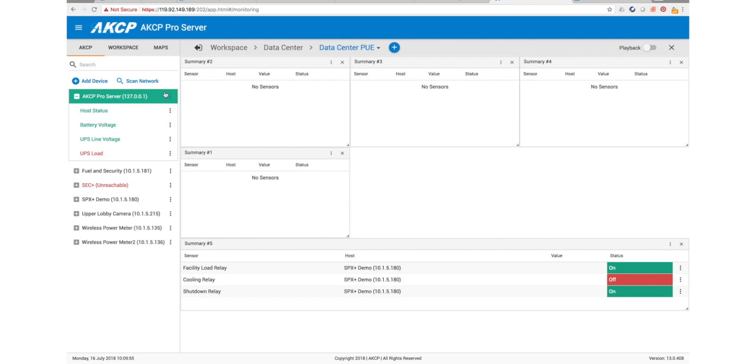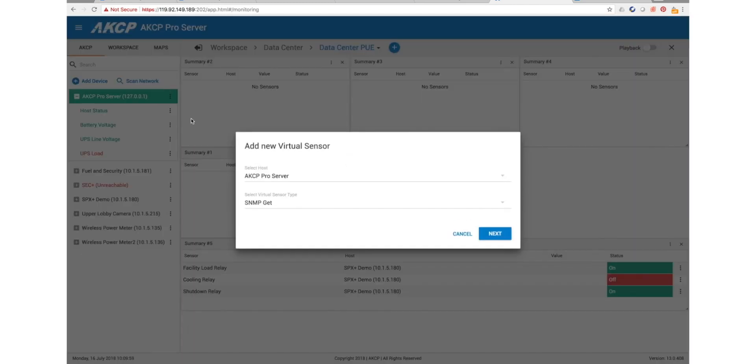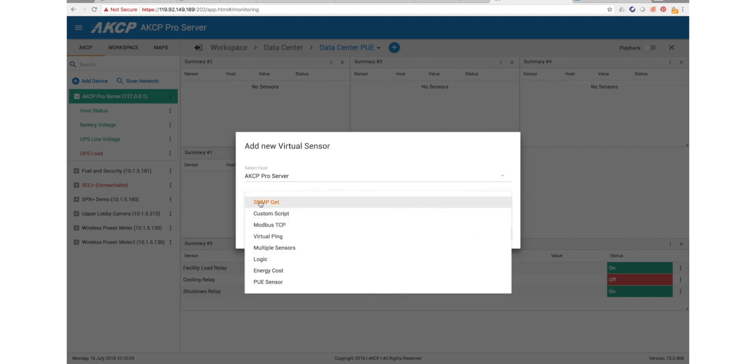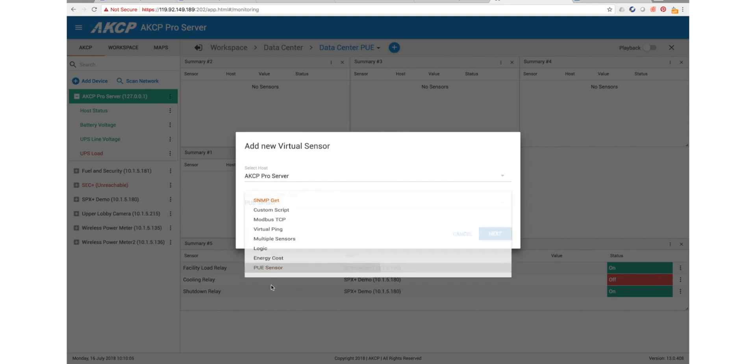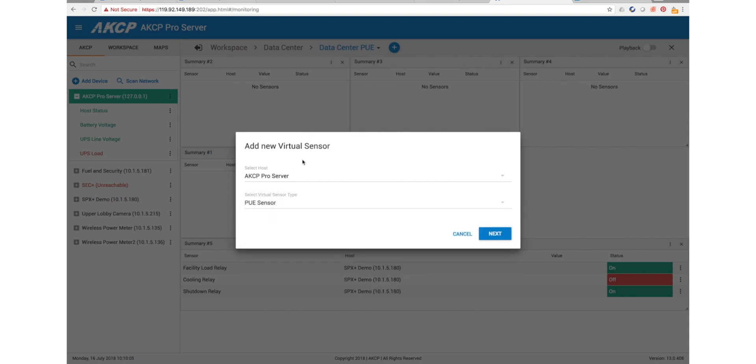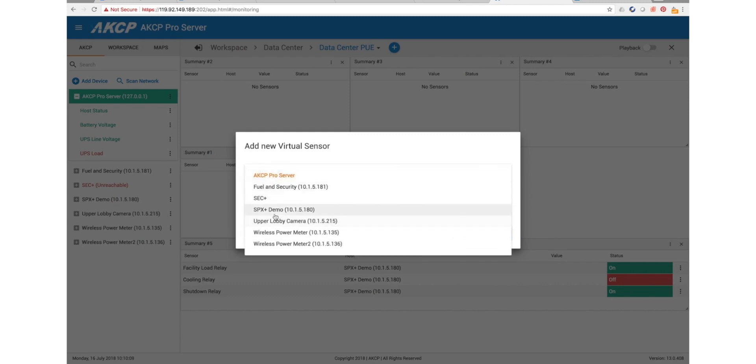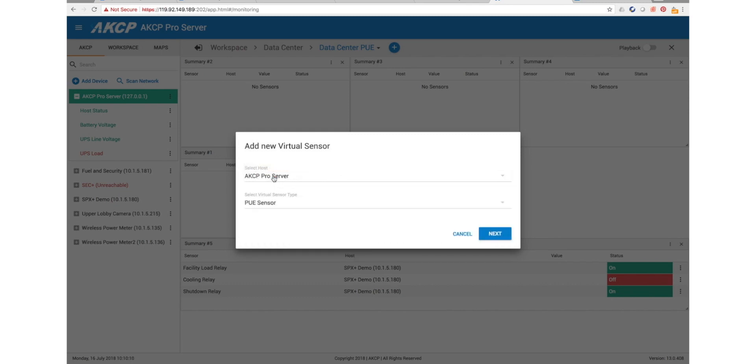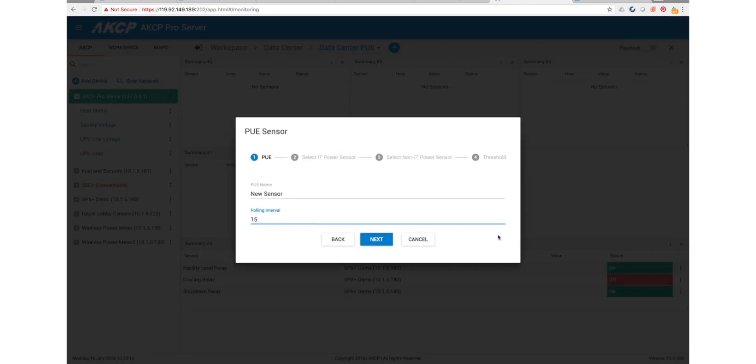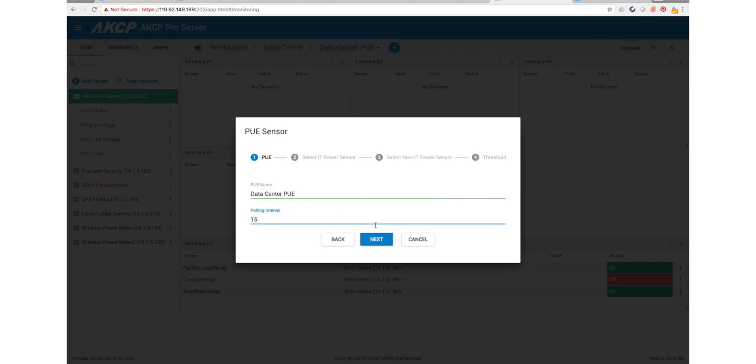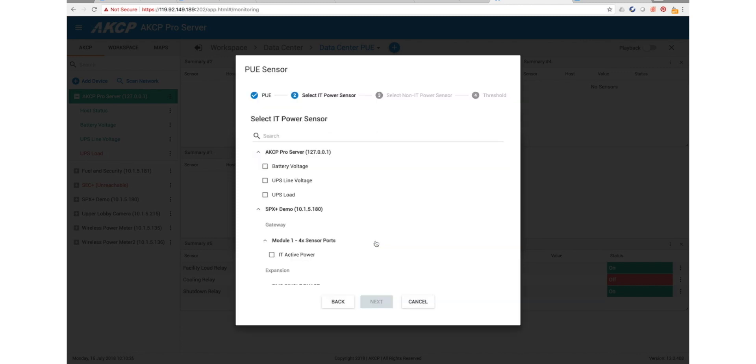To set up a PUE virtual sensor, we are going to select create virtual sensor. From our sensor type it will be a PUE sensor and the host this is going to be on is our AKCP Pro Server, which is where we've purchased already our virtual sensor licenses. We will call this our data center PUE and every 15 seconds will poll the data.